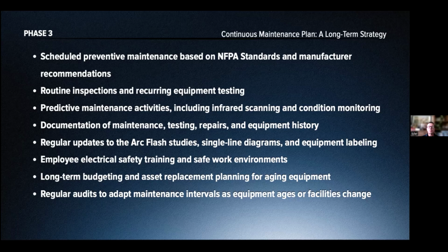Often you have tenants moving in and TI happens, and if you did your arc flash study 5 years ago, it's due for a revisit. Many TI contractors just put in whatever works to get the tenant power, but that could actually derate your arc flash study. So we want to catch that and be mindful, and make sure your single lines are up to date if equipment has been added to your system.